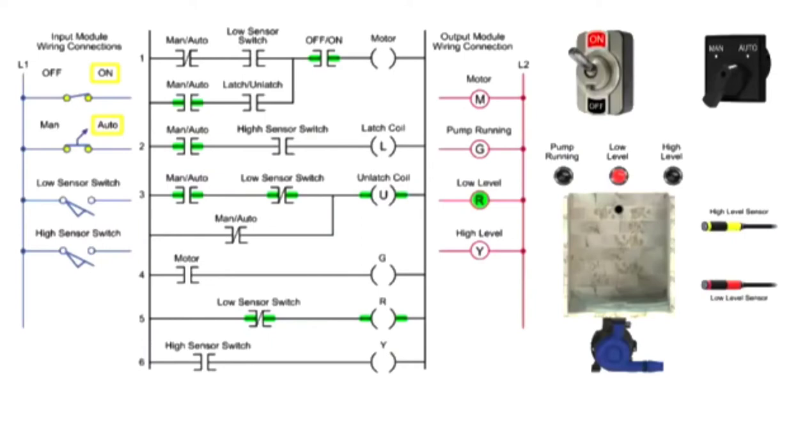As the water level rises, the low-sensor switch turns on, the red indicator lamp turns off, indicating the level is no longer low, and the internal bit is unlatched.